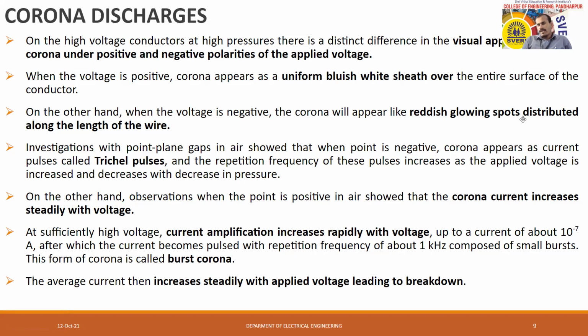If the voltage polarity is positive, the corona will have a bluish white sheath over the conductor surface, uniformly distributed. On the other hand, if the voltage is negative polarity, instead of bluish there will be reddish glowing spots distributed on the surface of the transmission line. So two important things we understood: one for positive voltage, another for negative voltage.